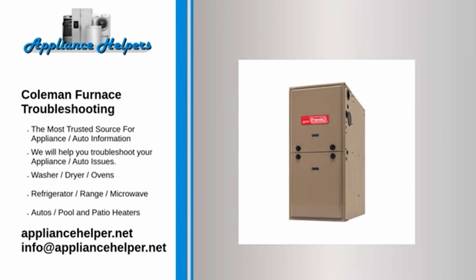If you're looking for help fixing your Coleman furnace, look no further. Our comprehensive Coleman furnace troubleshooting guide will explain common issues, provide tips, and show you how to read your model's error codes. Not heating. Either the circuit breaker has shorted or the unit's fuse has blown. Reset the circuit breaker associated with your Coleman furnace. If it's still not heating correctly, you'll want to replace the fuse.